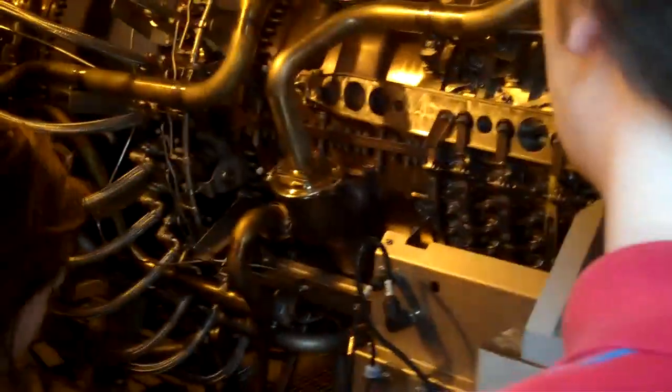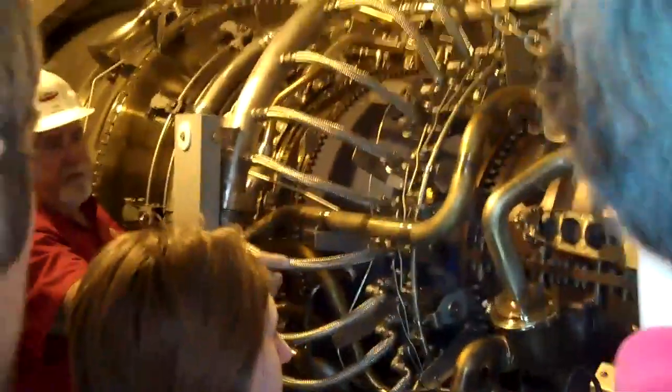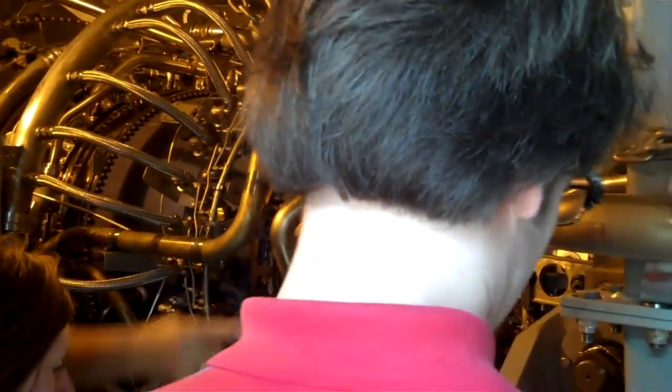One of the things about an axial compressor is you don't ever want the air to go backwards. The way this thing's set up is that the output of that first compressor, there's some little doors right inside this ductwork right here. When you're starting up, those doors are open, so you're just dumping all the air.